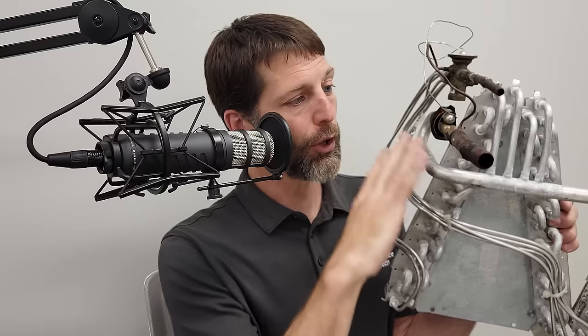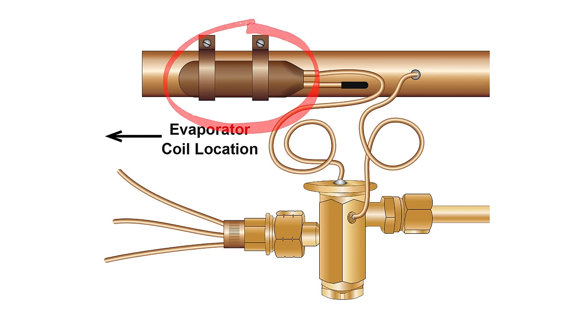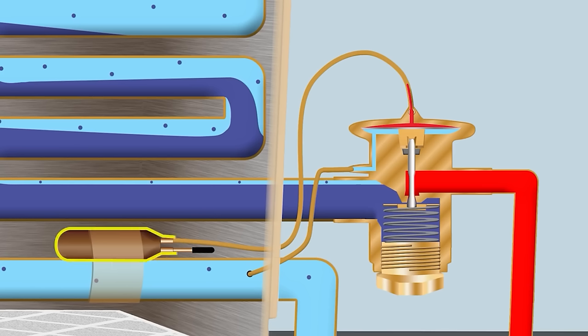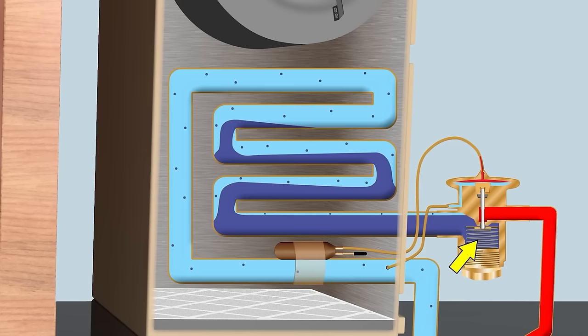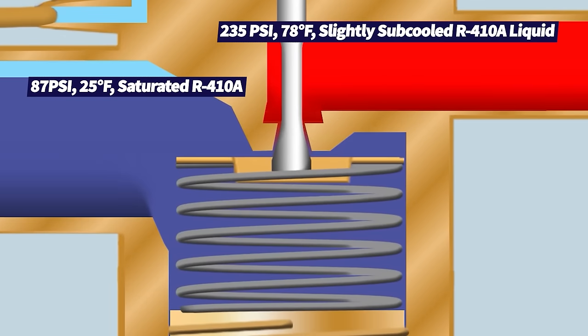Another refrigerant problem is at the thermostatic expansion valve. This type of metering device could have a clog in it, or it could be restricted because the little sensing bulb attached to the suction line has leaked out its refrigerant charge. This is called a liquid line restriction — even when you have the proper refrigerant entering, it's restricting the pathway too much, lowering the pressure too much.